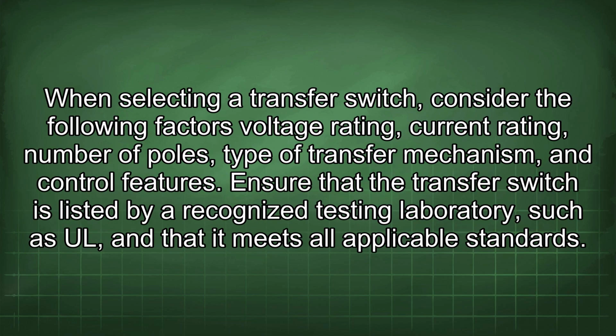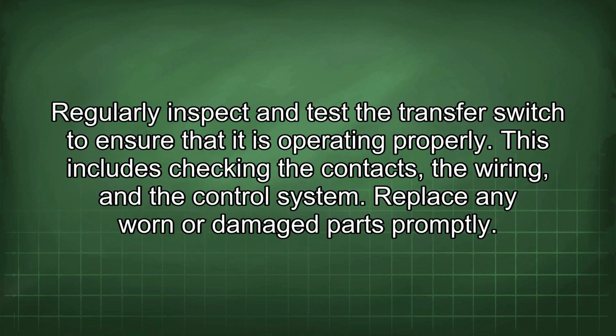When selecting a transfer switch, consider the following factors: voltage rating, current rating, number of poles, type of transfer mechanism, and control features. Ensure that the transfer switch is listed by a recognized testing laboratory such as UL and that it meets all applicable standards. Regularly inspect and test the transfer switch to ensure that it is operating properly. This includes checking the contacts, the wiring, and the control system. Replace any worn or damaged parts promptly.